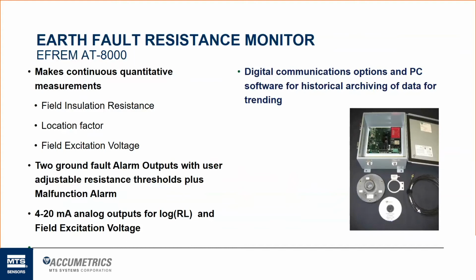We also offer 4 to 20 milliamp analog outputs, 2 channels. Channel 1 is for the field resistance, so that they can trend that historical information over time. And channel 2 is the field voltage. So many utilities use that feature. They interface that into their control room, and they're looking at that 4 to 20 current loop signal. And once it falls below a certain threshold, maybe 8 milliamps, 9 milliamps, something like that, they need to start paying closer attention because they're trending towards that ground fault.